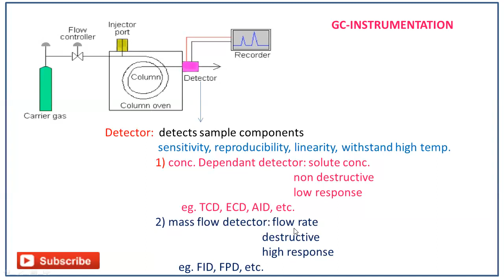While we are performing the experiment, we can get one problem. Sometimes we can see detector contamination. It is mainly due to carrier gas impurities. Sometimes the detector is not properly installed. So how do we know that the detector is contaminated or improperly installed? Sometimes we cannot get any peaks even when we are injecting the sample solution. That indicates the detector is not responding. Sometimes we get a low response due to the presence of higher impurities, due to passing of low grade carrier gases. These are the problems that we usually get. We can rectify them: we have to do proper installation and check the grade of the carrier gas. Then we can rectify these problems.